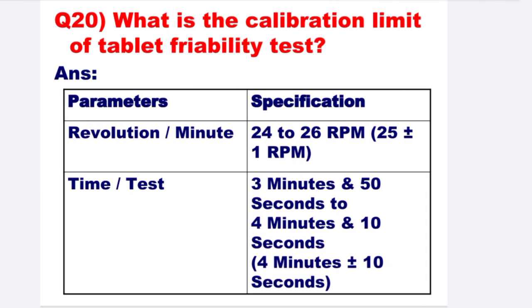And the last question: What is the calibration limit of tablet friability test? For revolutions per minute: 24 to 26 RPM. For timer test: 3 minutes and 50 seconds to 4 minutes and 10 seconds.